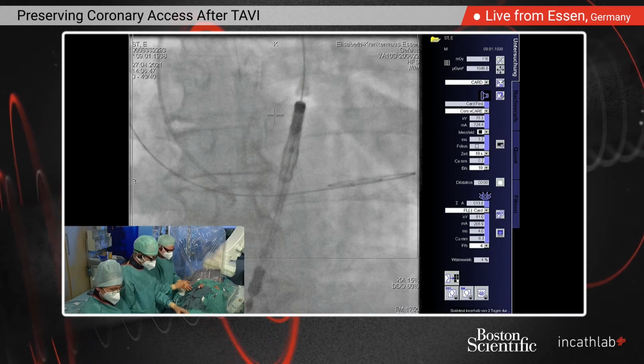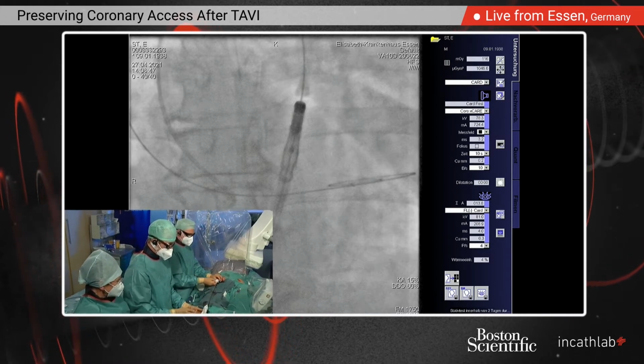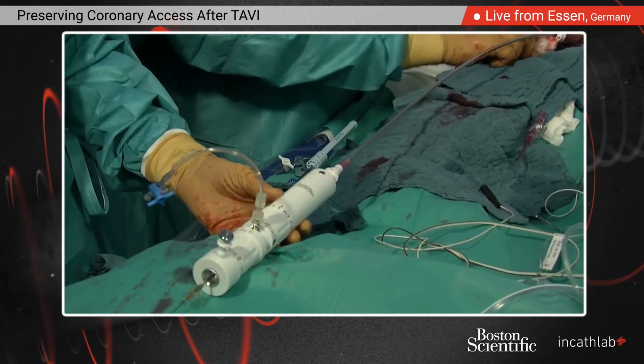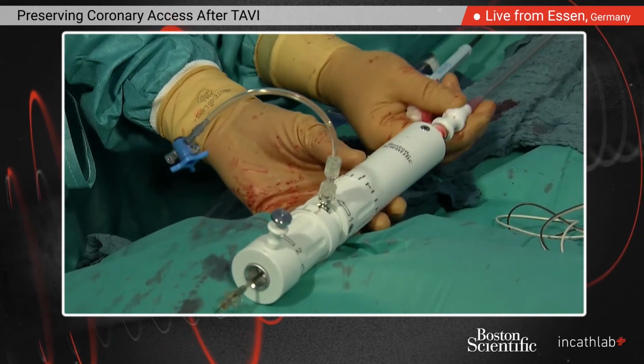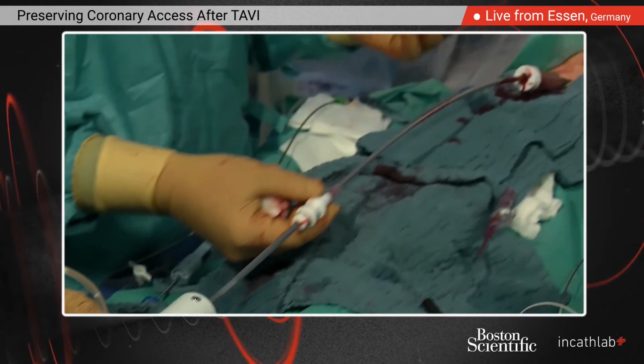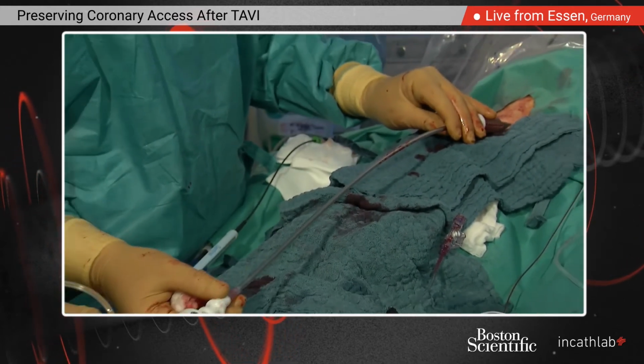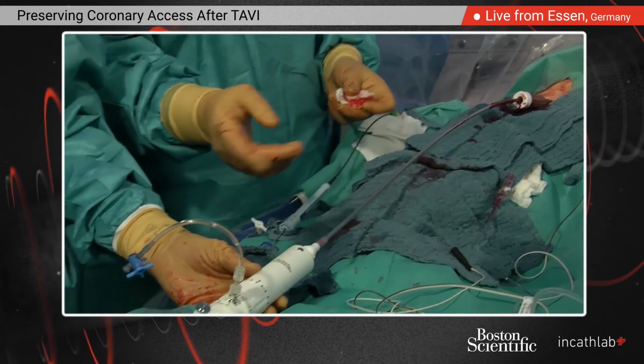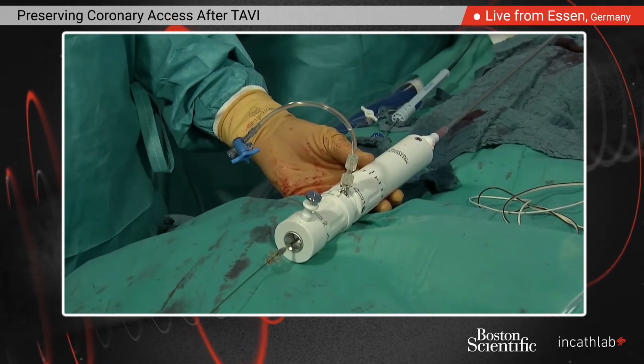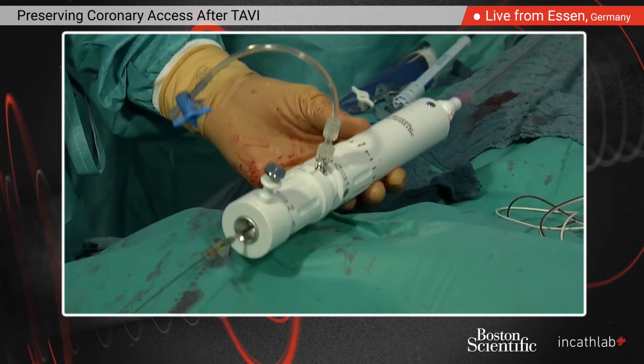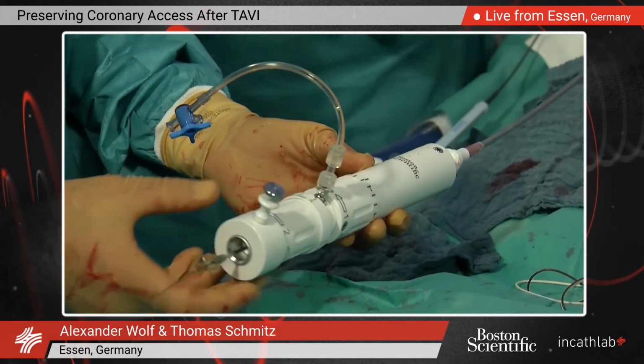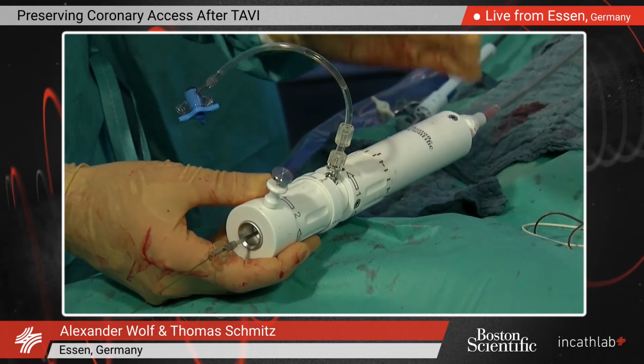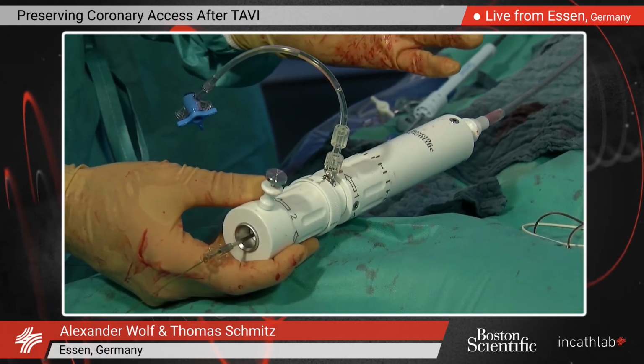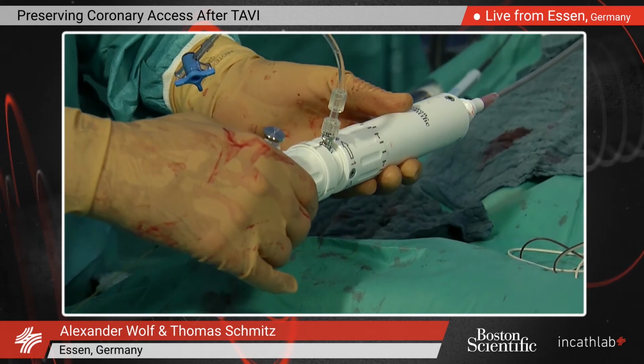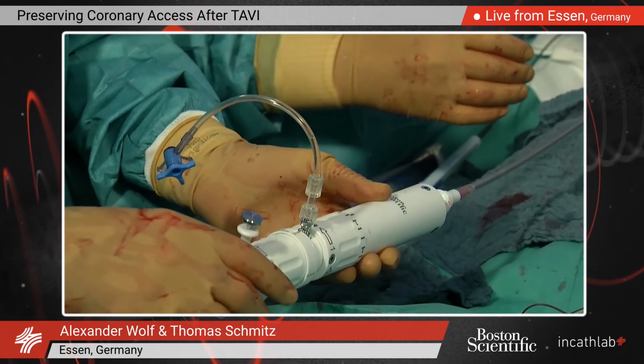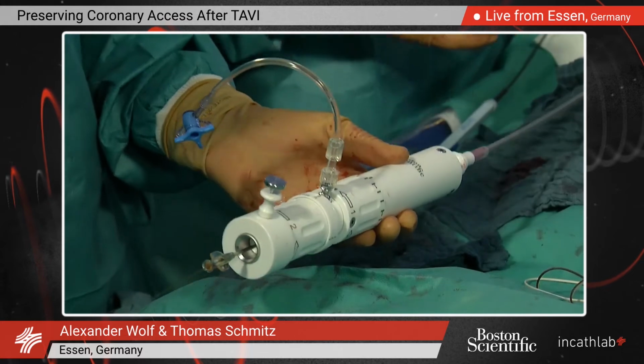Maybe we can introduce the delivery catheter, just for the audience which maybe does not know the device yet. So we have an introducer, which you have to put in the sheath. Once the valve is in, you can place this and park it here at the handle. And maybe Thomas, you can explain the two opening mechanisms on the delivery catheter. Yes, we have these two knobs. Maybe you can see it. First, we are turning knob 1, and the crown is opening to stabilize the valve in position. And then by turning knob 2, we are finally positioning the whole valve. So first 1 and then 2, but we will show it now live.